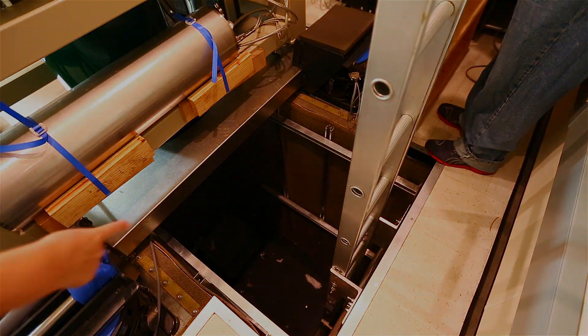You should not feel any kind of vibration coming from the surrounding environment — from the building or from the street that is close by. You should be completely isolated. The better you can isolate your microscope, the better it will work, and you will be able to see things that are otherwise in the background of noise.